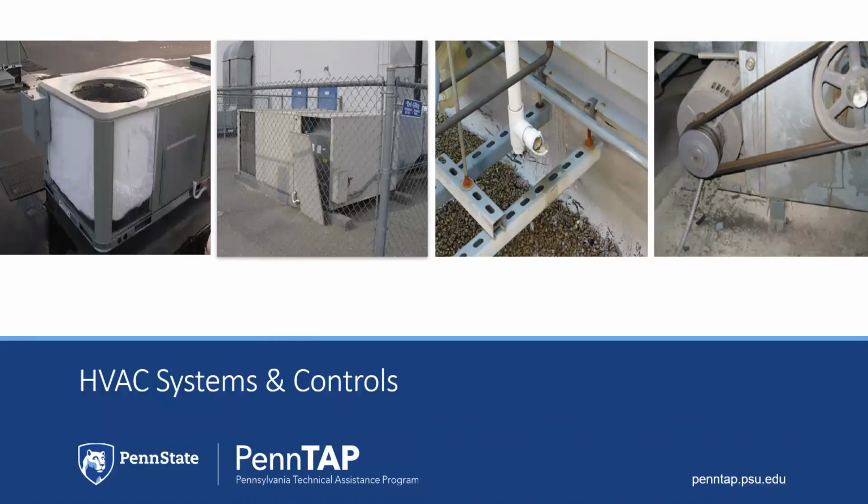Then we have incomplete maintenance where the doors weren't put back on. You never know if the doors weren't put back on. You can't say a few days later that the conditions are sound. Something could move in, leaves and debris could get in there. You don't really know, you don't have that control anymore.